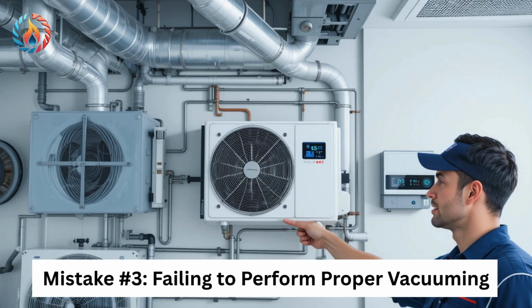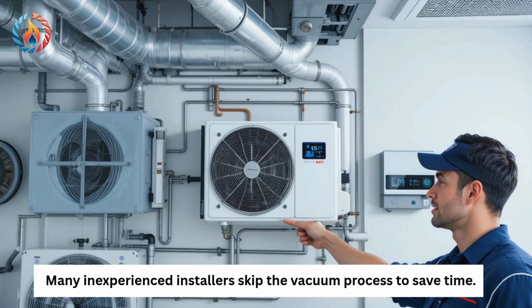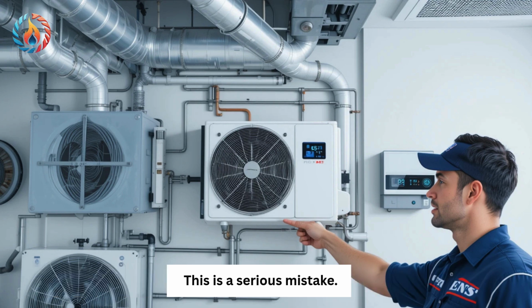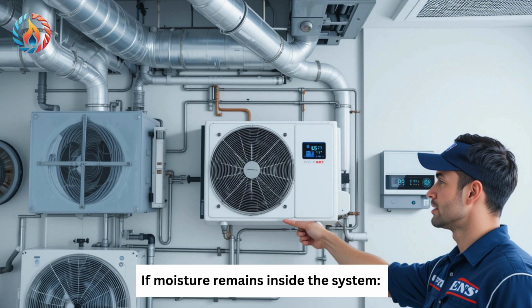Mistake number 3. Failing to perform proper vacuuming. Many inexperienced installers skip the vacuum process to save time. This is a serious mistake. Vacuuming removes air, moisture, and non-condensable gases from the refrigeration system. If moisture remains inside the system, acid formation may occur, internal corrosion may develop, and system performance may decrease.